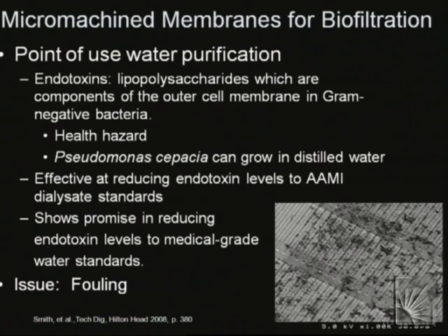And one thing that will happen to filters is that, if they're effective, they will block the unwanted stuff, and if they're really effective, block a lot of it, all of it. But in the process, they may become fouled. And when they become fouled, they become blocked. And when they're blocked, they're not effective. The system would shut down.